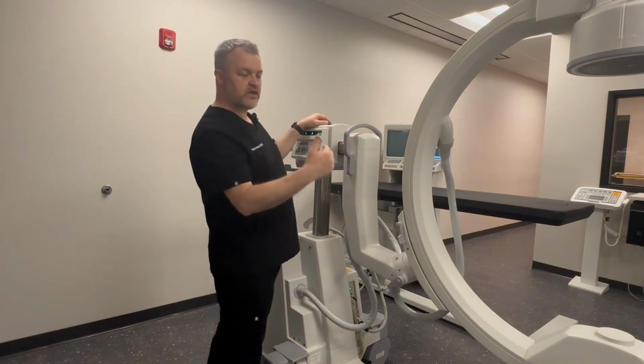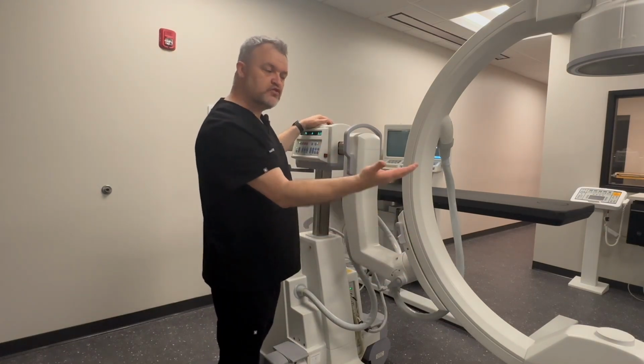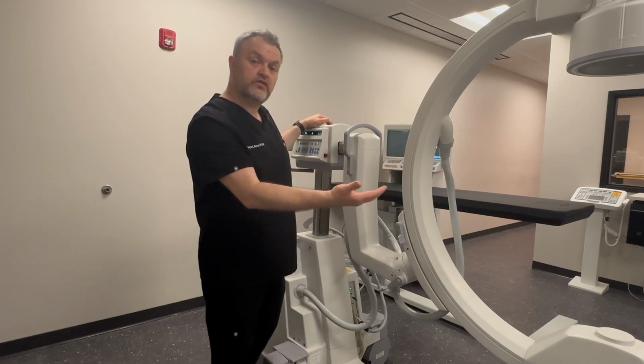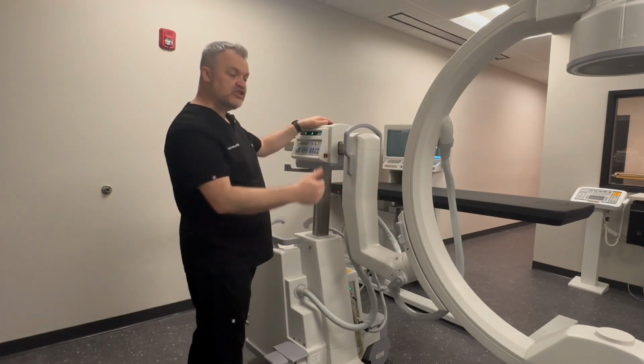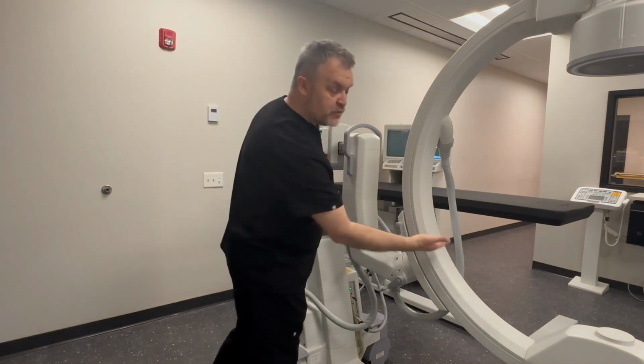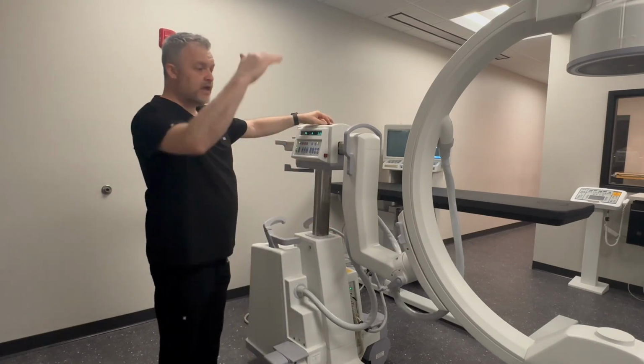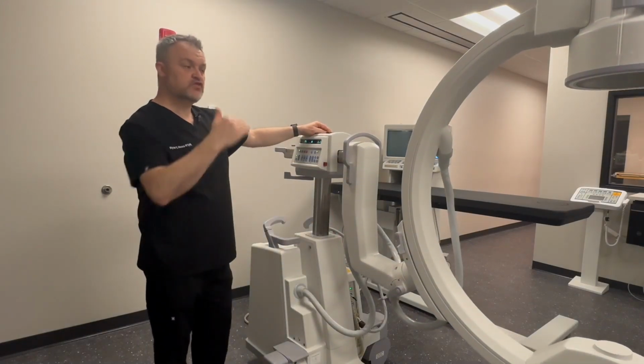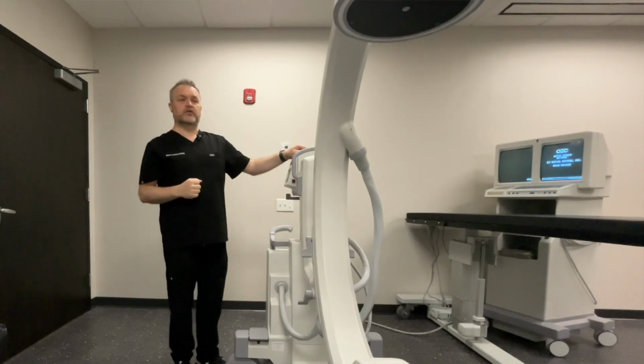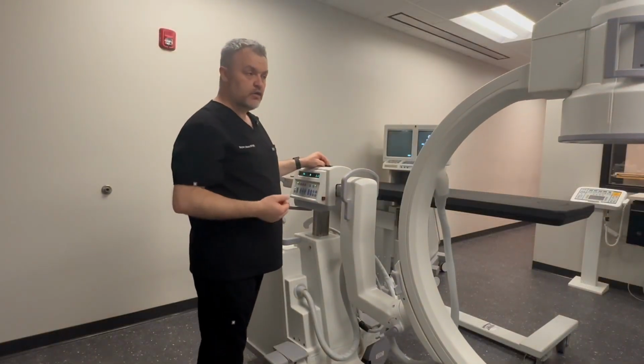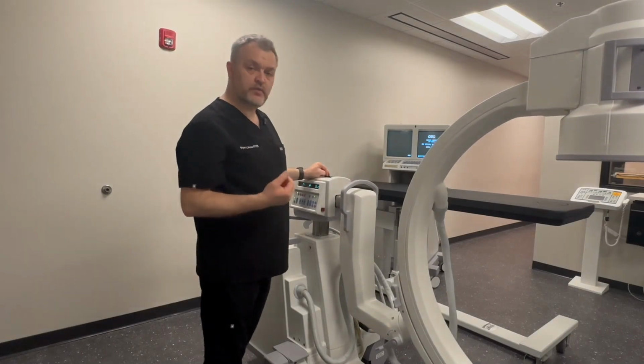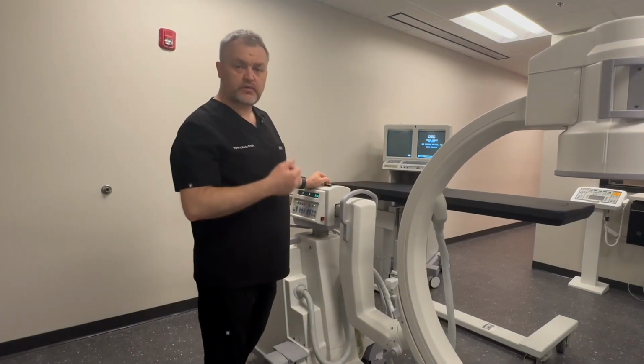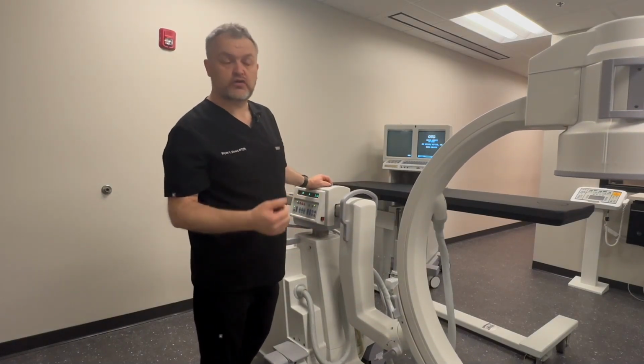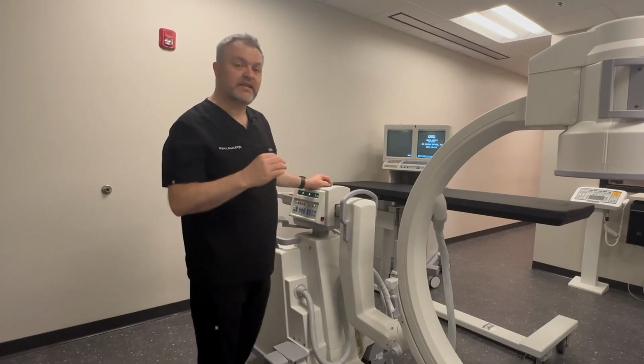And you also have to be careful of how far the tube is raising up underneath the patient or underneath the bed. Because with its C shape, you don't want the C to be pressing up against the bed. And then we have an opposite function where we can lower the height of our C-arm. So this feature for raising and lowering would be the height function, and that would be the instruction: raise up, drop your machine, lower your machine, some things like that. But height is the function.